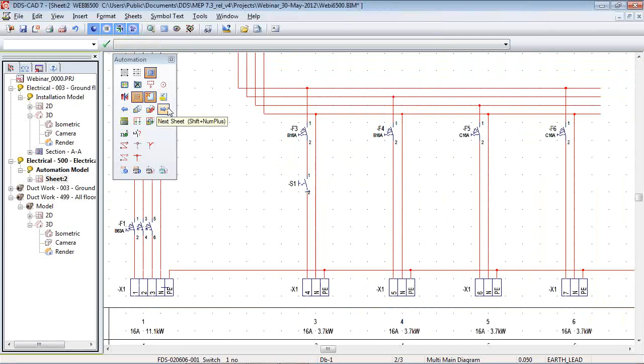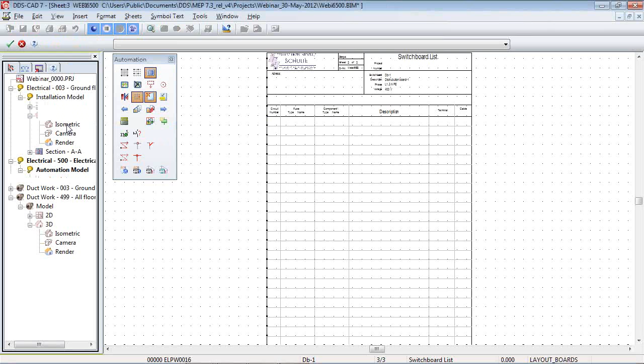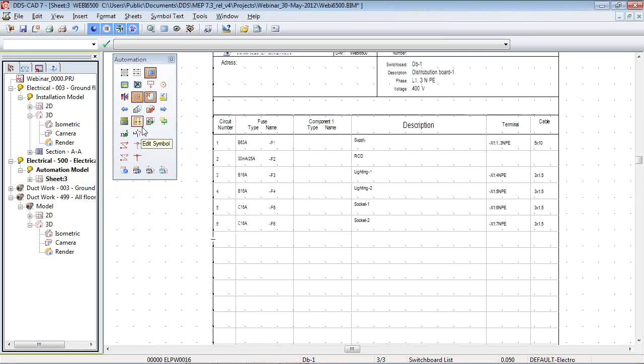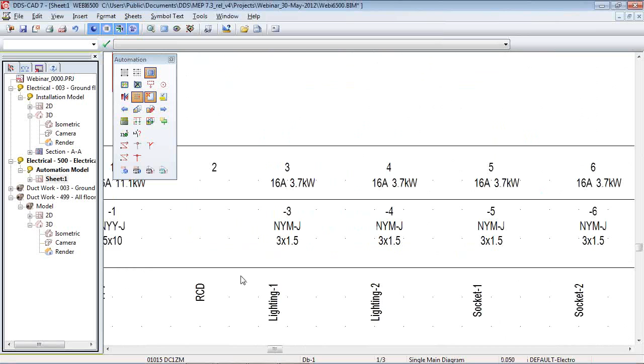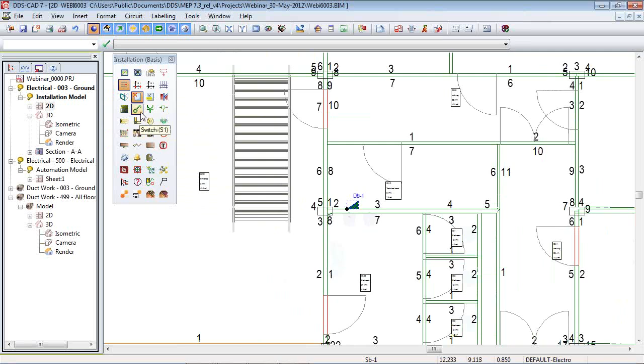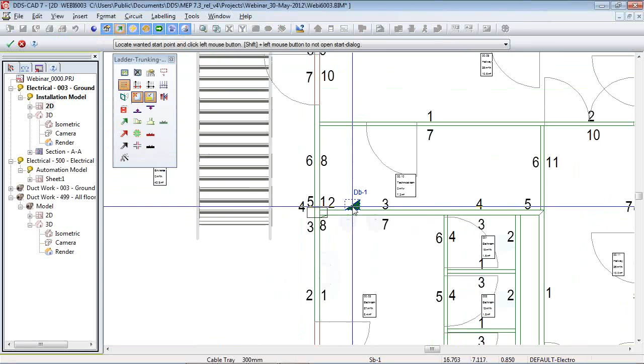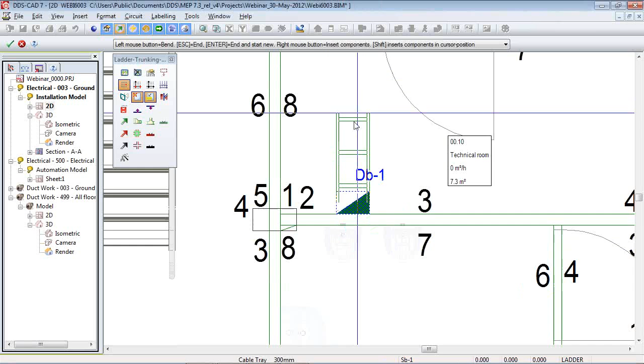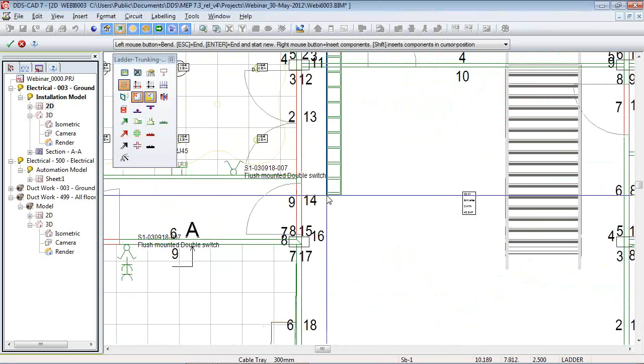So when I insert a single line diagram or a multi-line diagram in combination with my switchboard list, I can define a schematic view of my circuit board. So my circuit board is defined like this: we have the B-type circuit breaker 63, our RCD 25, and our B-type single core for lighting 1, lighting 2, socket 1, socket 2. You can also see that we have cables attached. This is our single line diagram, and we can also automatically create our multi-line diagram from our schematics.